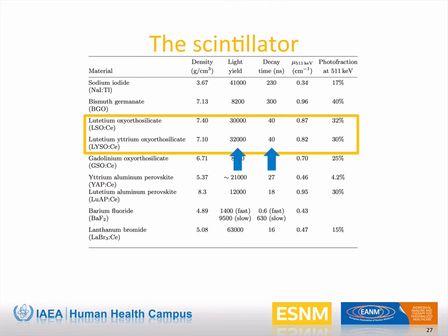The light yield has influence in measuring the energy with a very high energy resolution, and together with the short decay time, it is ideal to measure the arrival time with great precision, then having a very high timing resolution. However, BGO is still used in modern PET systems mainly for its advantages in terms of detection efficiency.